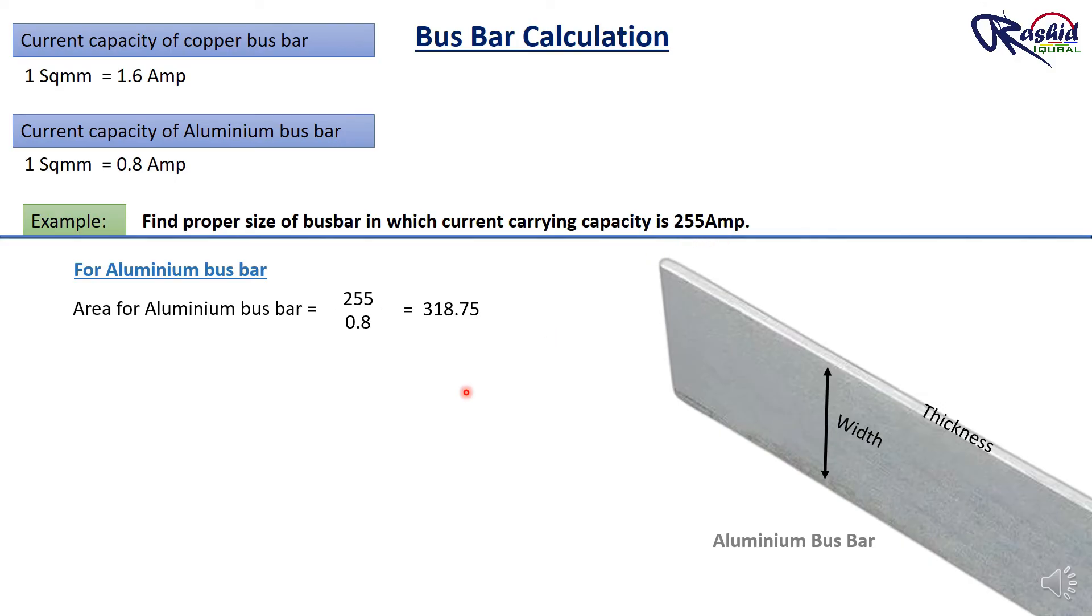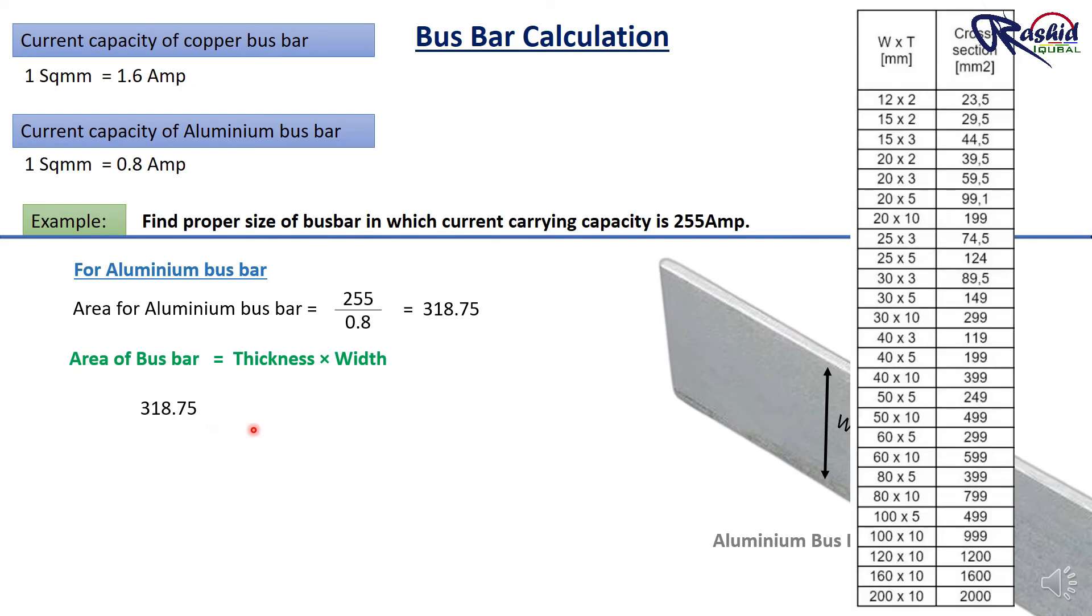So to find the suitable size of aluminium busbar, we use the formula same area equal to thickness multiplied by width. And we have calculated the area that is 318.75 square mm. And we are choosing a thickness of 10 mm. It depends on you. You can choose as per your load, as per your current carrying capacity or as per your requirement. But here I am choosing 10 mm.